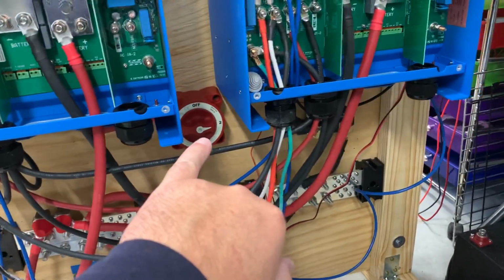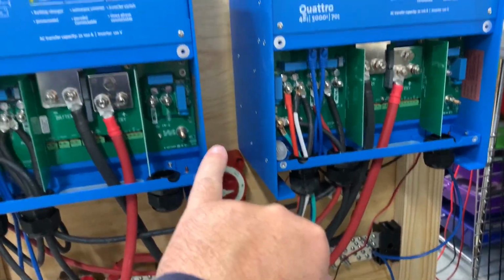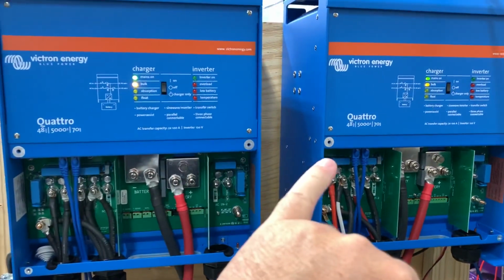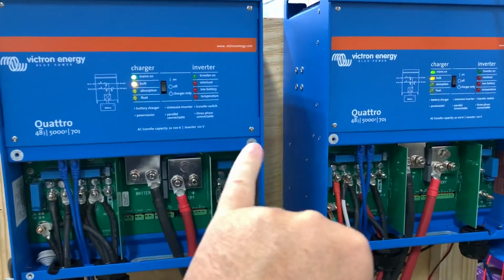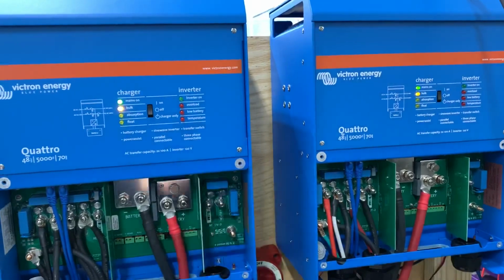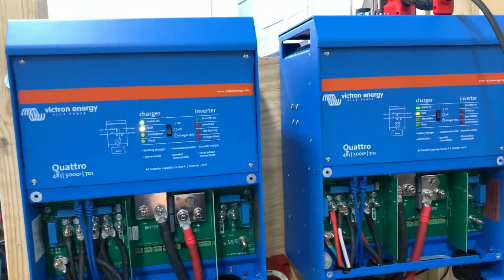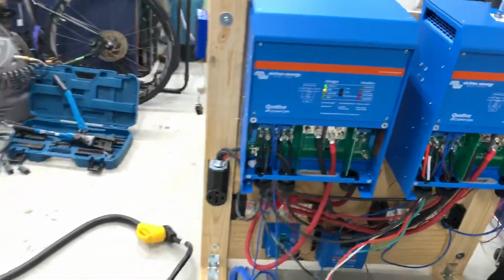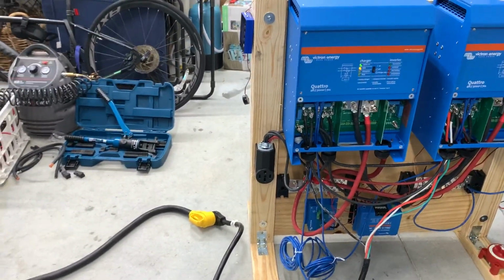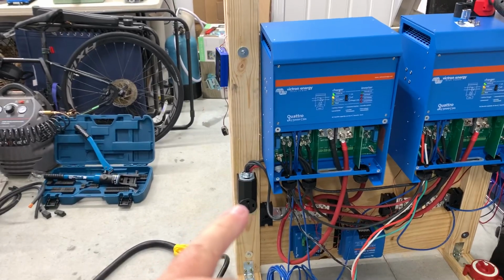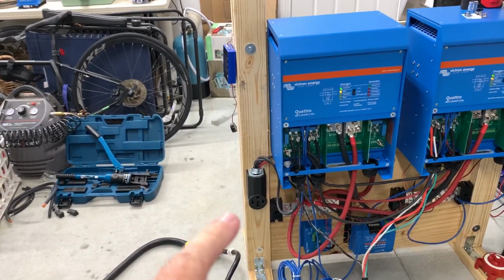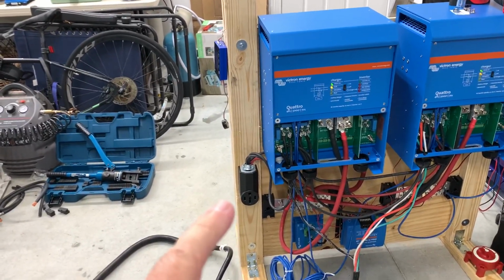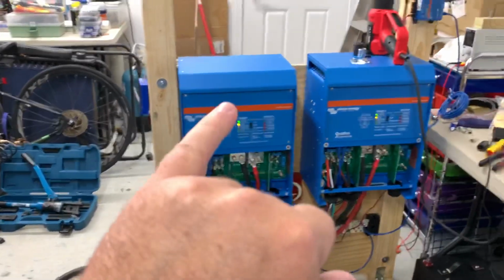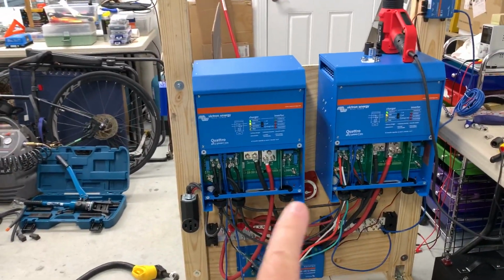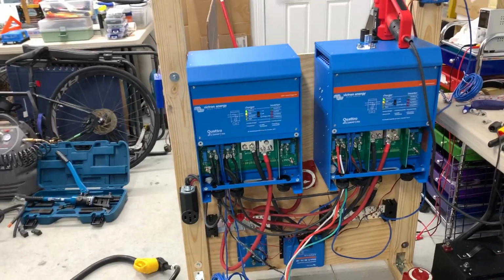So I have 2 inverters, not only so I can have 8 kilowatts, 4 each, but they are operating in sequence or in pair with each other to create split phase 240 volt power. Normally that's not necessary on an RV, but in mine it is, because the mini split air conditioning is actually 240 volts. So I'll be able to feed 120 and 240 from this system.